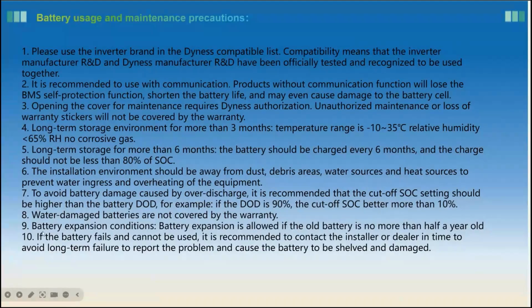Okay, battery expansion. Usually if a customer purchased one battery and used it for 1 or 2 years, and wants to buy another battery to expand the capacity, in these cases we recommend no more than half a year, because the longer you use a battery, the capacity of the new battery and the old batteries will be different. If they continue to use them together, as time goes by, the SOC may show differently because the battery capacities are different.